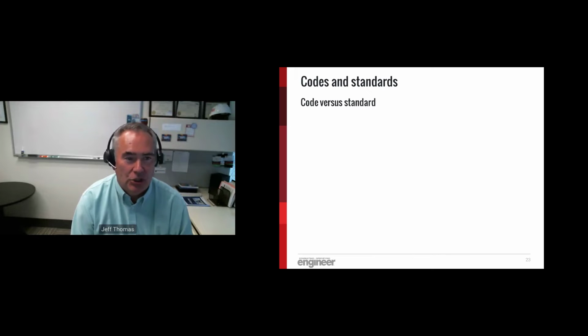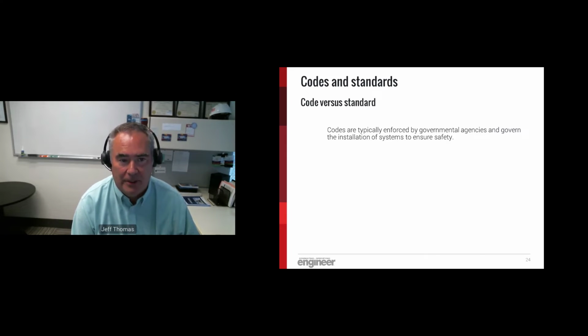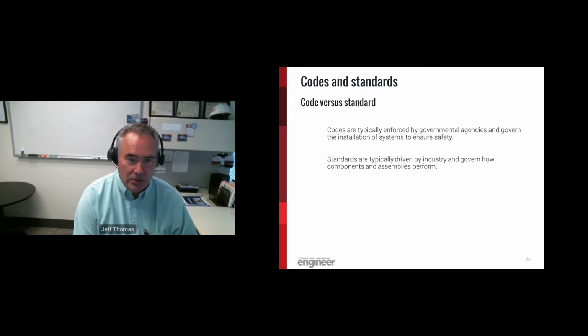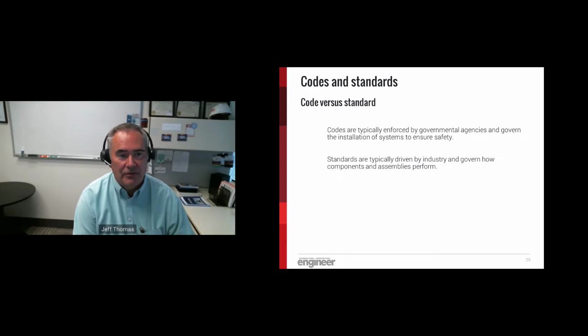So you heard John mention codes and you heard John mention standards. So let's talk about the differences. Codes typically are enforced by governmental agencies and govern the installation of systems to ensure safety. Everything you heard John talk about with the NEC, it talked about safe operation, protection of this, protection of that. That's what codes are for. Standards are typically driven by industry and govern how components and assemblies perform. You heard him talk about UL 489. You heard him talk about other standards that govern how the breakers operate. And if a breaker is going to operate in a particular way, it must do this and do that to meet the standard. Those are two very different things, but they both play a part in our design work.